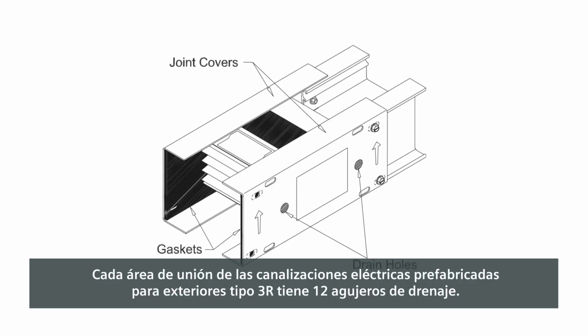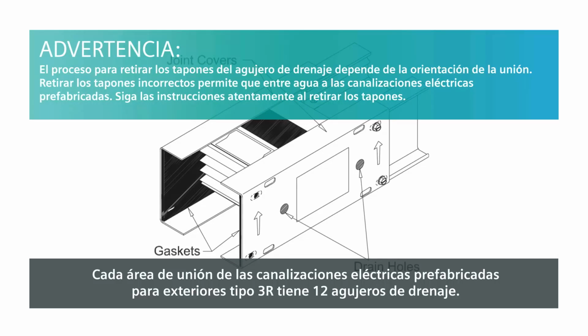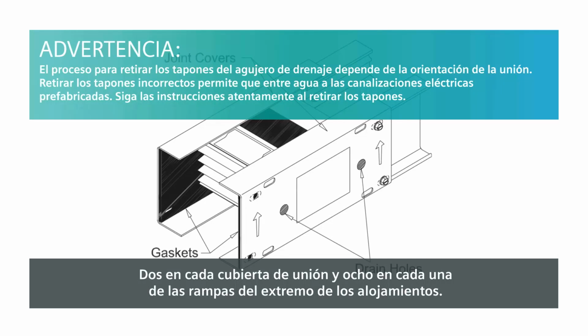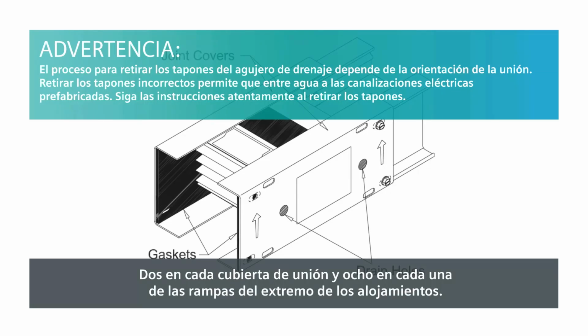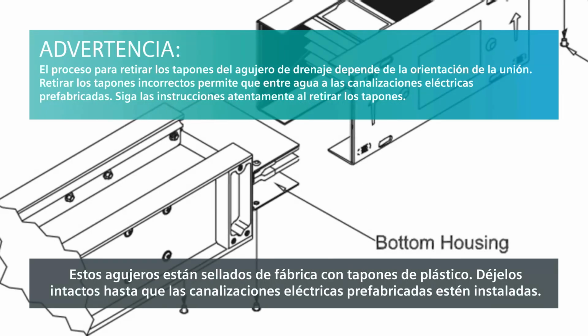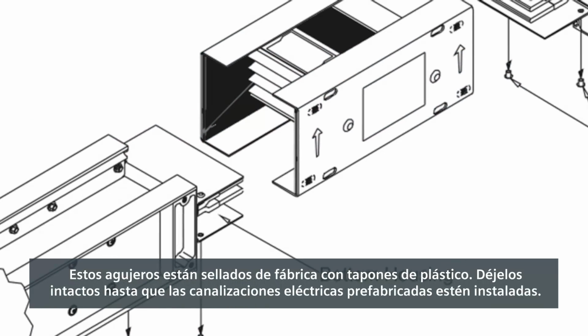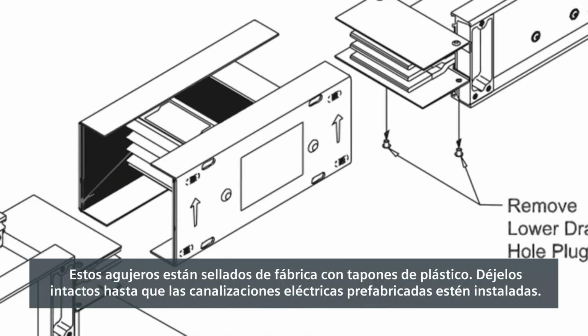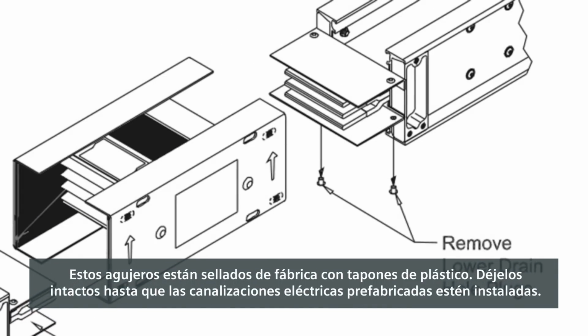Each joint area of 3R type outdoor busway has 12 drain holes, 2 in each joint cover and 8 on the end ramps of the housings. These holes are sealed with plastic plugs from the factory. Leave them intact until the busway is installed.